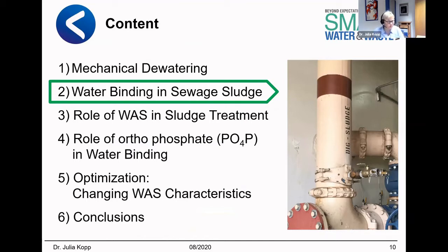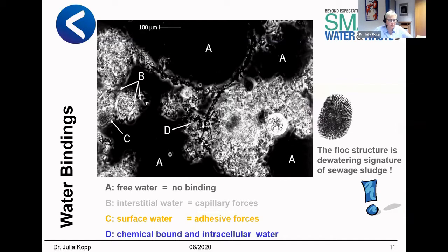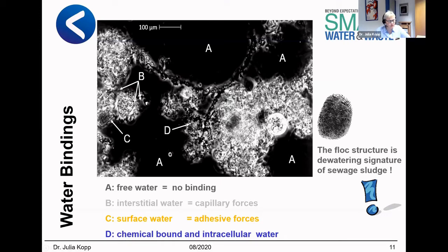If you talk about sludge dewatering, you have to talk about the water binding. Even after dewatering, if you have 25% dried solid in your sludge cake, you still have 75% water. Here you see a microscopic picture of sewage sludge showing different parts of water in relation to physical bonding. The water with no relation to sludge particles can be separated by mechanical forces. The most interesting part is the interstitial water, captured inside the sludge particles. Surface water is bound by adhesive forces, and there is chemically bound intracellular water — the binding is so strict you are not able to release it by mechanical forces.